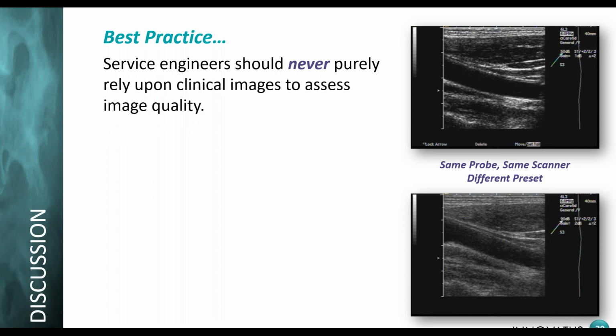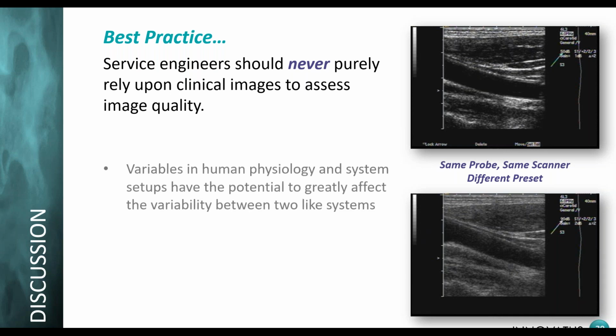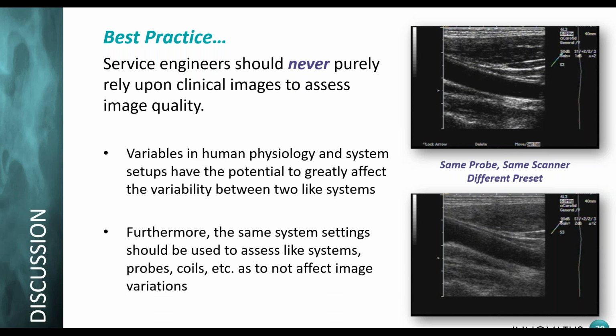So service engineers should never purely rely on clinical images to assess image quality. The reason for that, this is the exact same person, me. It's the exact same machine, exact same probe, exact same everything, except for presets. I changed the presets on the machine a little bit. There are tremendous amounts of variables in human physiology and system setups. So unless you really know what you're doing, you should be using an ultrasound phantom, because phantoms do not change, and always use the same settings.